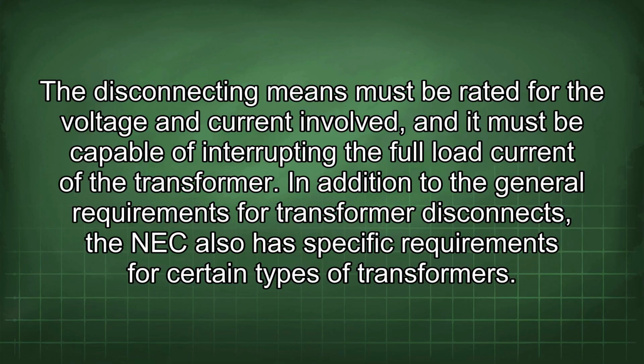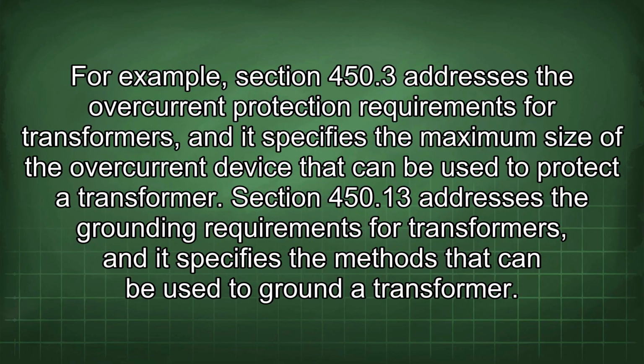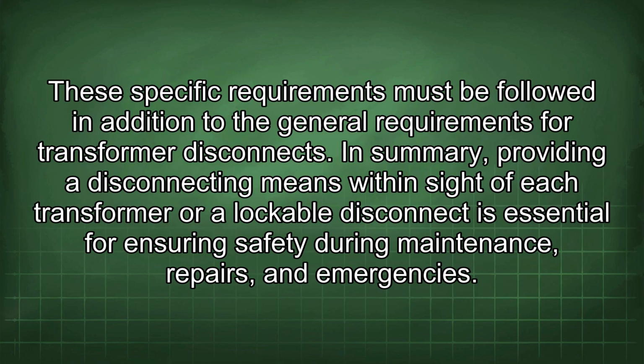In addition to the general requirements for transformer disconnect, the NEC also has specific requirements for certain types of transformers. For example, Section 450.3 addresses the overcurrent protection requirements for transformers, and it specifies the maximum size of the overcurrent device that can be used to protect a transformer. Section 450.13 addresses the grounding requirements for transformers, and it specifies the methods that can be used to ground a transformer. These specific requirements must be followed in addition to the general requirements for transformer disconnects.